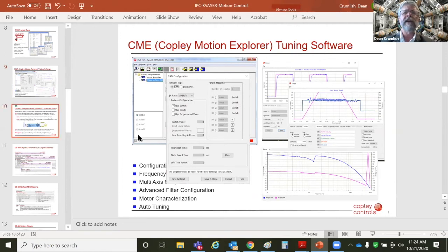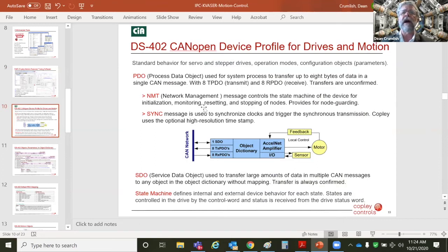I'm going to talk about the DS402 protocol as briefly as possible. This is looking under the hood, right? So there's a bunch of messages on the network. You've got PDOs, process data objects, which we map, 8 transmit, 8 receive. These are the important things that we need for the process of motion control. We also have network management messages, for initializing the devices, moving the state machine through the different states of pre-op, op and safe state. We can monitor, and we can do resetting and stopping of nodes through the NMT. And there's a sync message.